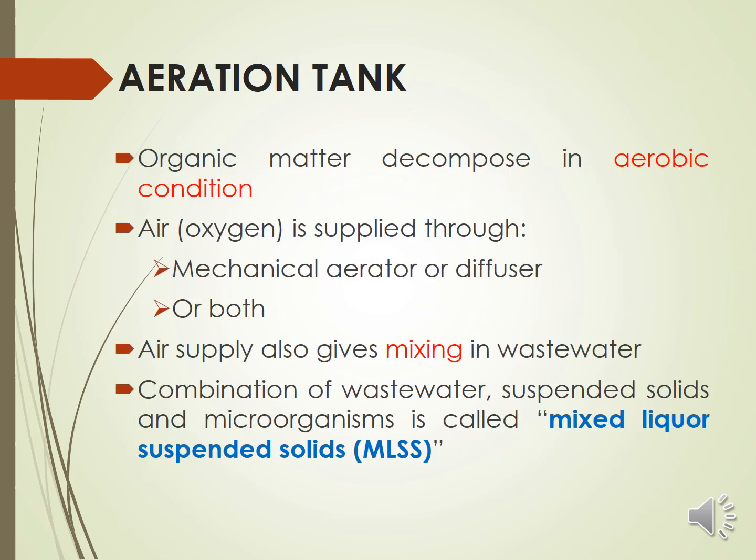In the aeration tank, organic matter is decomposed under aerobic conditions where oxygen or air is supplied. Air supply is accomplished through mechanical mixing, air diffusers, or both. The air supply also enhances mixing between the microorganisms and the wastewater. From this point on, the combination of wastewater, biomass, and microorganisms is called Mixed Liquor Suspended Solids, or MLSS. The terms biomass, MLSS, and suspended solids are essentially equivalent at this secondary treatment stage.